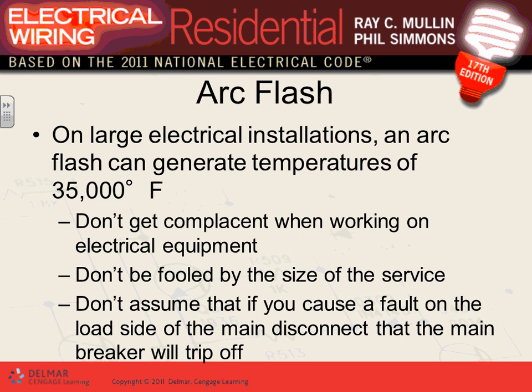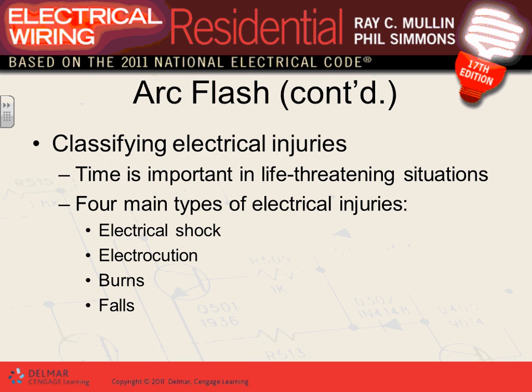And before you even use the meter, you know what they want you to do? Before you use your meter, you need to go verify that your voltmeter is working. What if your voltmeter is not working? You are to go to a known source, like an outlet. Check your voltmeter. Yup, it's giving me a voltage. Yup, it's working. Then you go check for the voltage. So they want to make sure when you work on an energized object, that piece of equipment is completely de-energized.